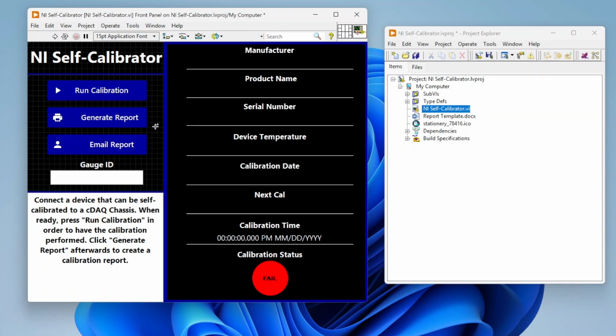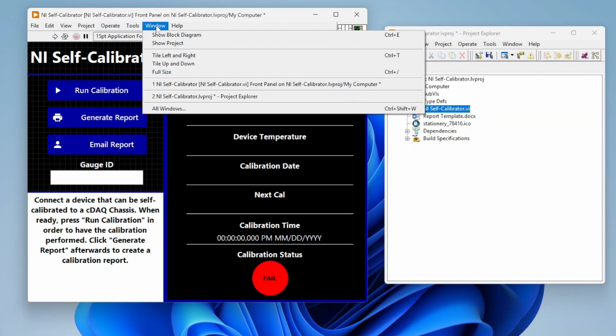And on the right side here, we have all this information: the manufacturer, the product name, serial number, temperature, the date, the next cal date, the time, and whether it passed or failed. And again, this doesn't replace external calibration. It's really just for managing the self-calibration. I think typically on the self-calibratable devices, don't quote me on this 100%, but I think they extend the external calibration frequency due to the self-calibration.